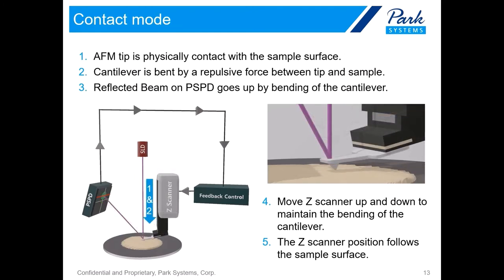Here is the simple procedure of contact mode. The AFM tip physically contacts the sample surface, and the cantilever is bent by the repulsive force between tip and sample. The reflected beam on the PSPD goes up by bending of the cantilever, and the Z scanner moves up and down to maintain the bending of the cantilever, following the AFM sample surface.